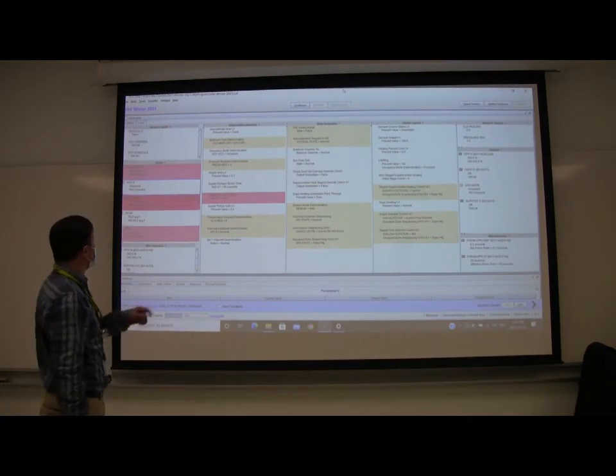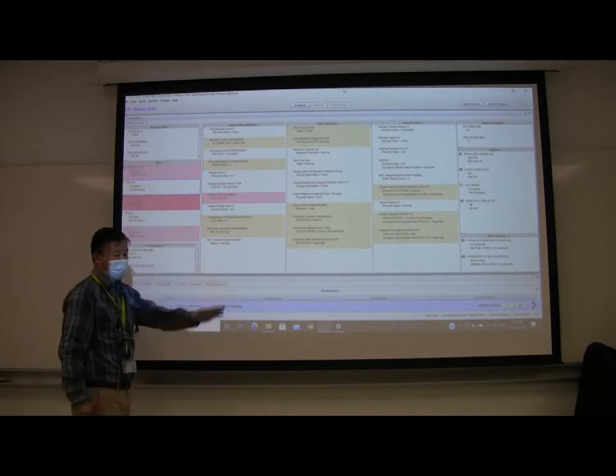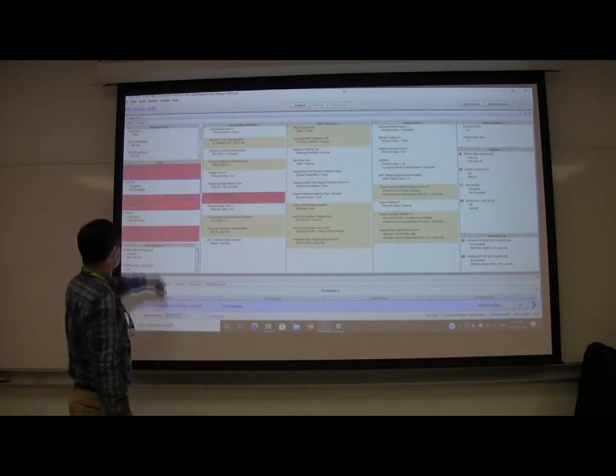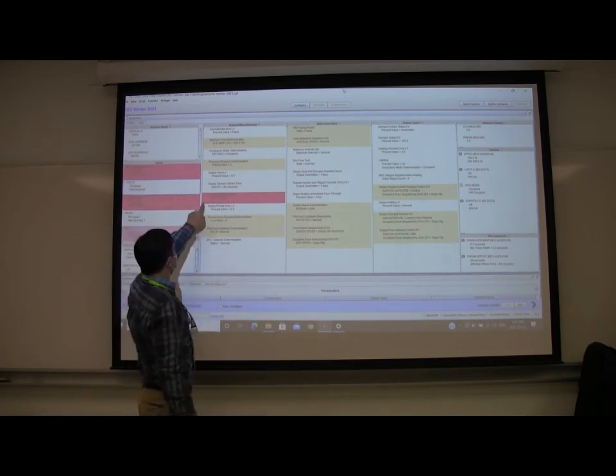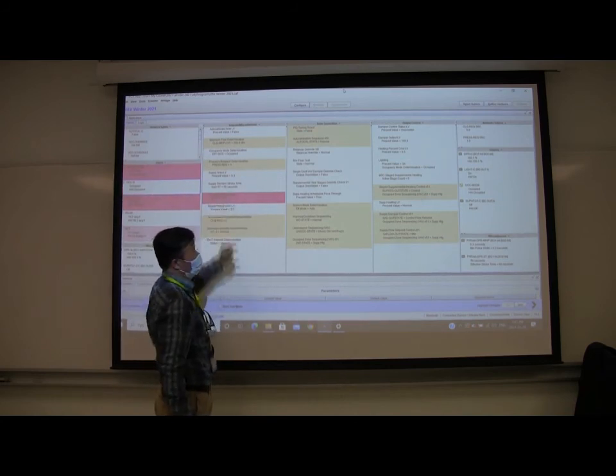Now we have commissioned the discharge air. You can see here the motor, the blower, is stopped. You can see the input here, discharge air velocity pressure is 0.01. So you can see the airflow, this amount here.